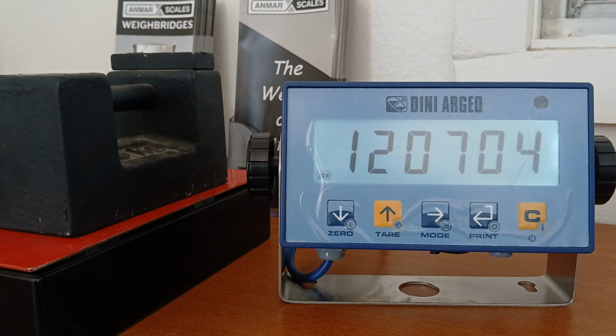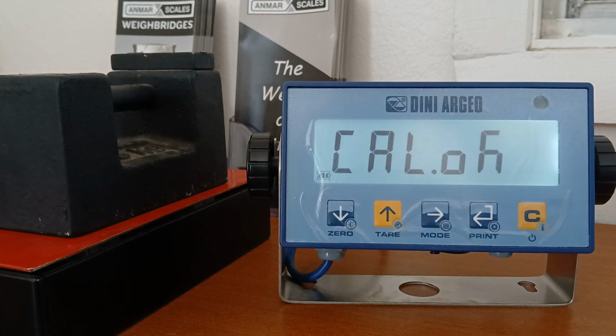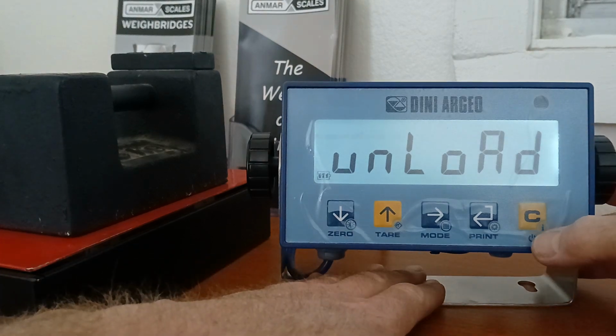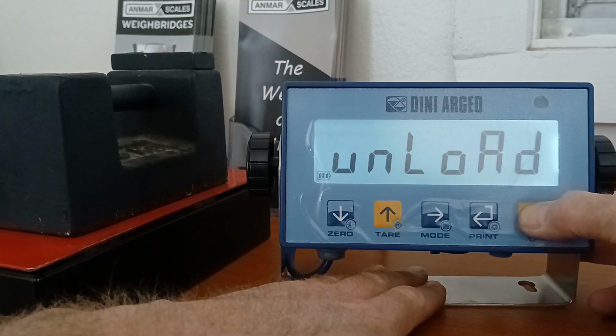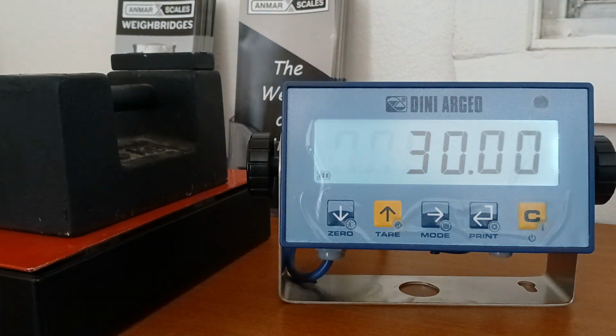Again, the scale flashes some numbers and a few different screens. You come up and it says cal OK. At this point it says unload. Now the calibration is completed. If we take the weight off the scale, it will automatically save the calibration data and come back to normal weighing. If for whatever reason we can't unload the scale, we need to leave the calibration weight in there for a while, we can just push the C key and it'll store it and come out of it.